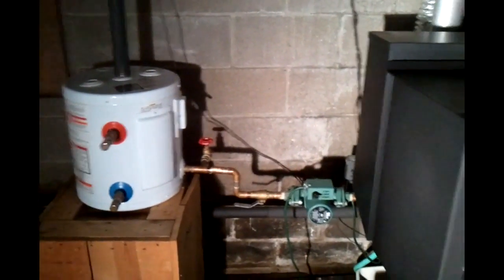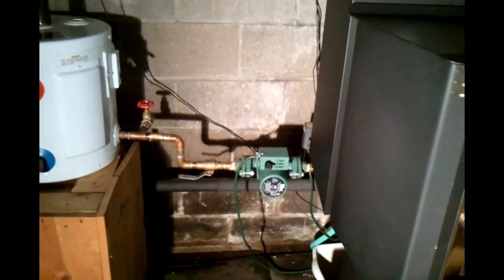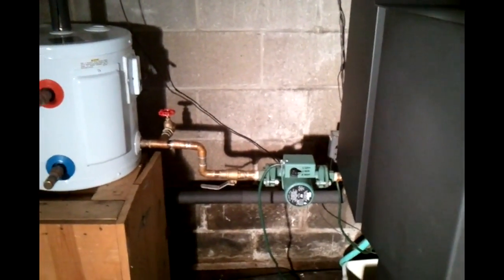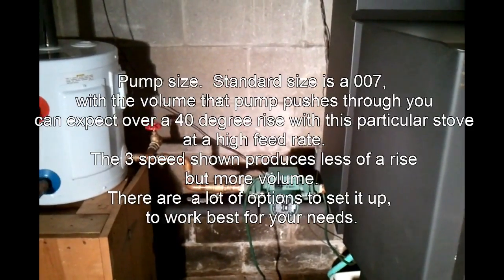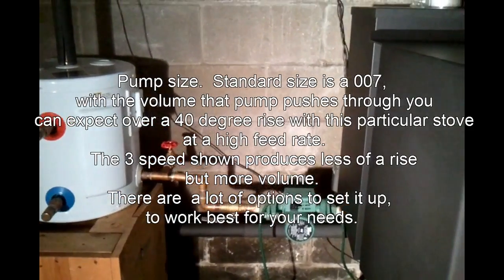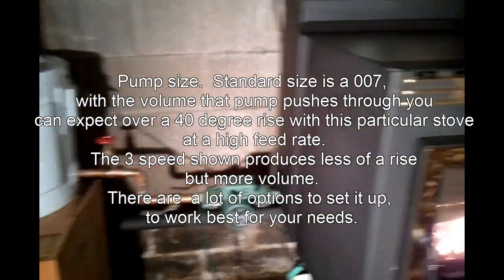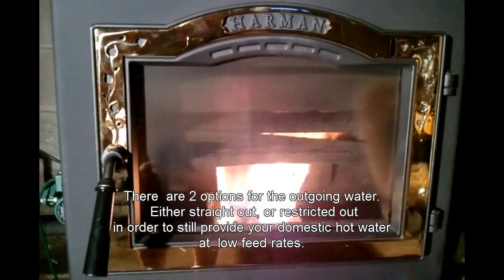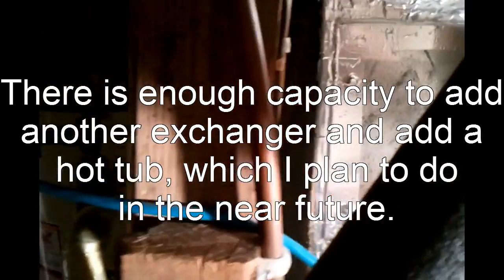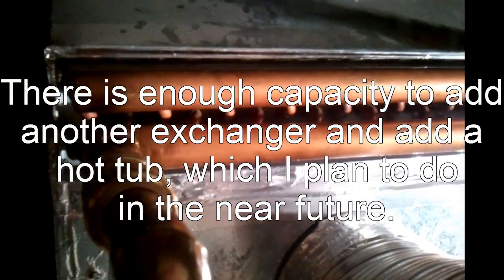But starting here, the water would be pulled from the 6-gallon tank. Typical pump used for this setup would be a Taco 007. I have a 3-speed just because I was playing with the settings and tweaking it a little bit. So from there, the water is pumped into the stove through the mixing plate, then through the coils, and then it comes out and travels through the 3/4 inch copper pipe. The hot water comes up to the water to air heat exchanger that I installed in the furnace plenum, and then it'll come back to the 6-gallon tank.